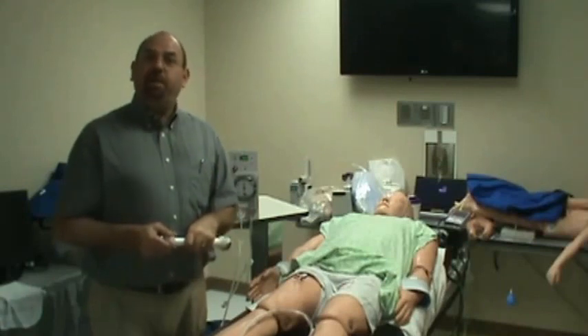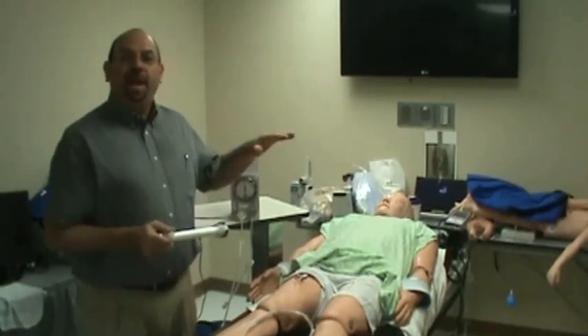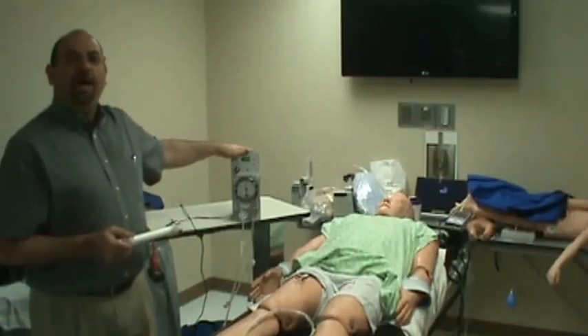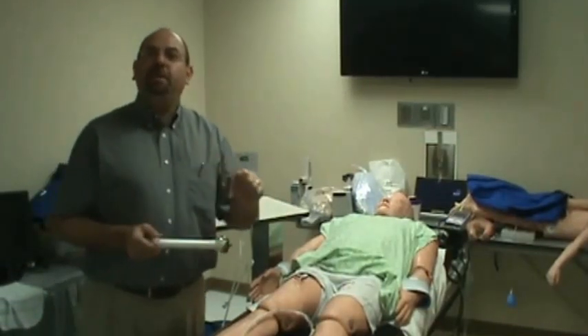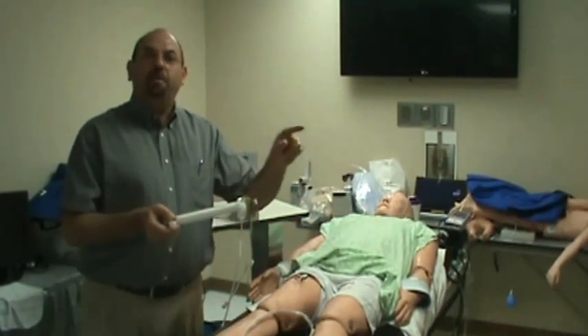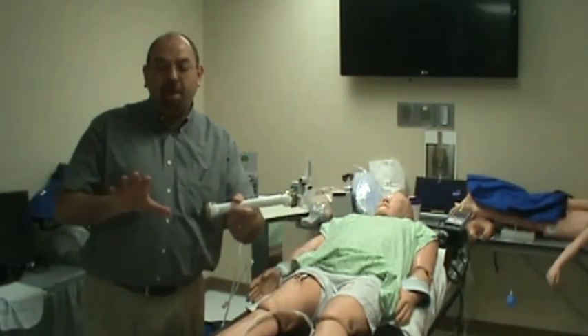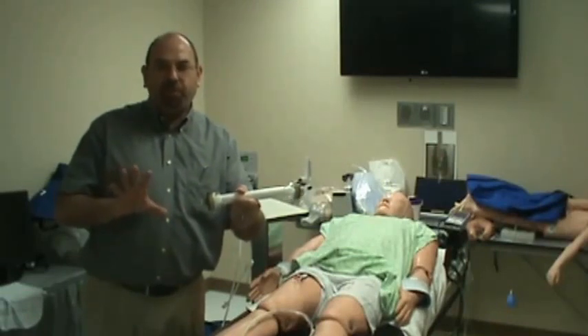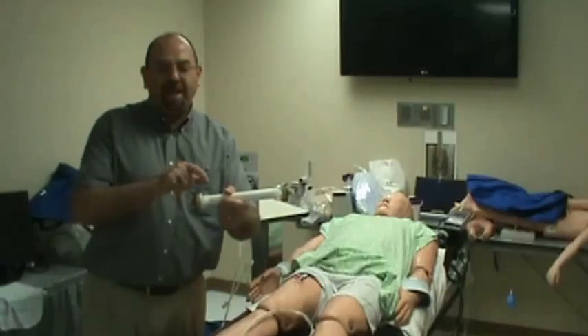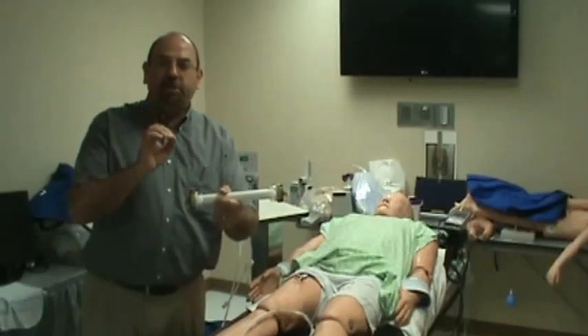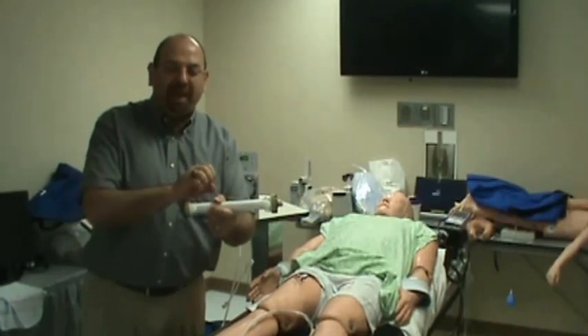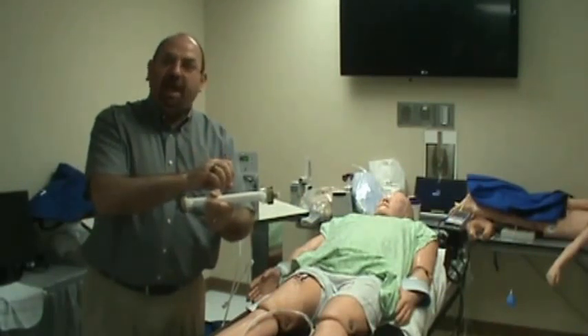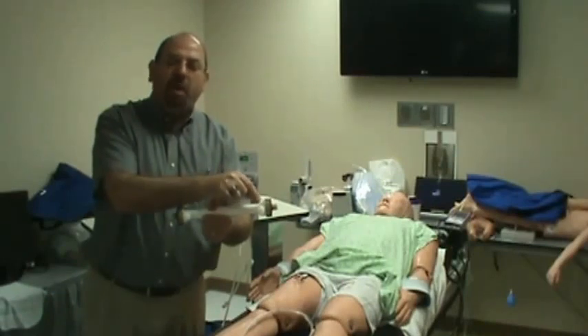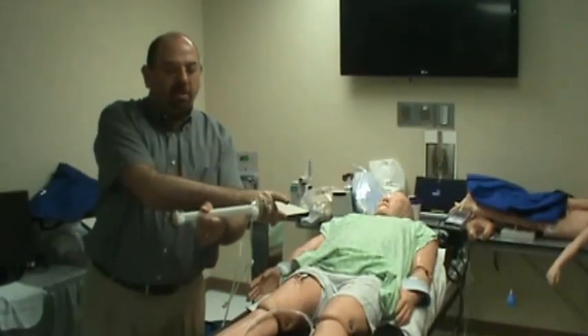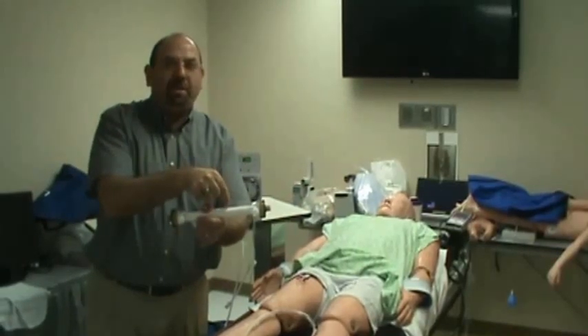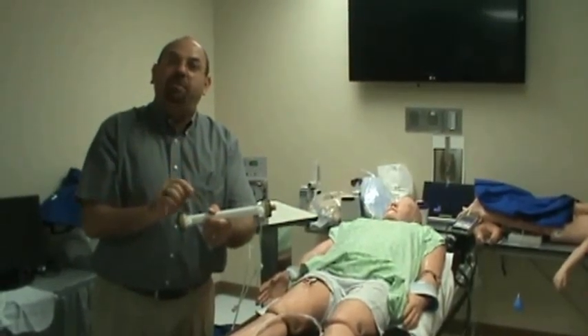CVVH-f is a lot more dependable, with much less risk, and you have the pump to utilize as a form of propelling the blood from the venous system through the filter back into the venous system. Again, the pump has to be pre-filter, because when it's pre-filter right here, it pushes the blood, and the pressure within the fibers is going to be a positive hydrostatic pressure, and that allows the convection and allows the filtration to leak out from one end of the filters. If it's placed here, then there is suction, and the pressure within the fiber is going to be negative, and you would not be able to have filtration.